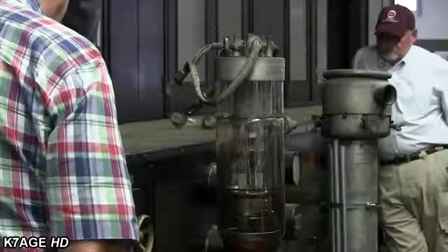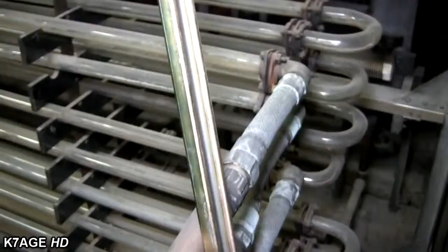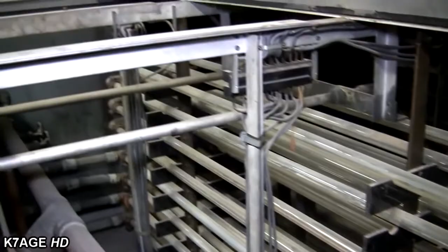When you go by here a little later, we'll walk around and go behind the transmitter, and I'll open some doors to show you the back of the power amplifier. You'll see a lot of Pyrex tubing here. There was about 12,000 volts DC on these tubes, so the water touching them and flowing over them to cool them had to be distilled water, very pure, and there had to be a long creepage or insulator path in the form of Pyrex tubing or spiral wound ceramics to get the voltage from ground potential up to 12,000 volts and back safely.